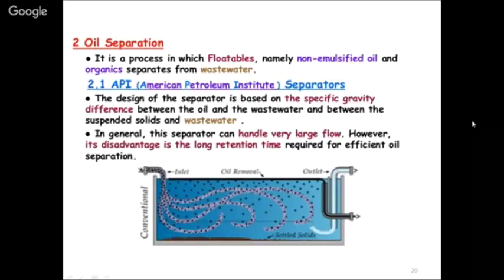Oil separation deals with floatable, non-emulsified oils. Two methods are used. The first is the American Petroleum Institute (API) separator: a tank in which oil floats to the top and is skimmed off. The design is based on the specific gravity difference - oil is lighter, so it rises. It can handle large flows with no restriction; it is just a tank designed so that oil automatically comes to the top for skimming. It is the simplest method.